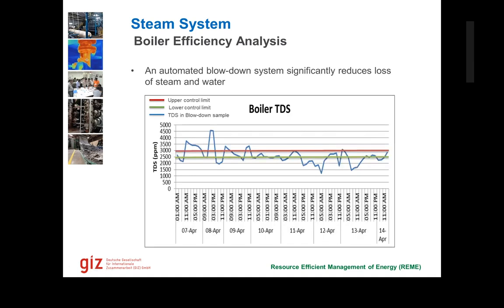And then blowdown. We're all aware of the automated blowdown. People are very, very hesitant, but you can see this factory was doing a manual blowdown. According to them, they had set an upper control limit of 3000 ppm TDS and a lower control limit of 2500 ppm. They wanted to keep the boiler blowdown TDS within this range, but you can see the actual values. I can only see 8 data points within that range. All of them are either above or below.